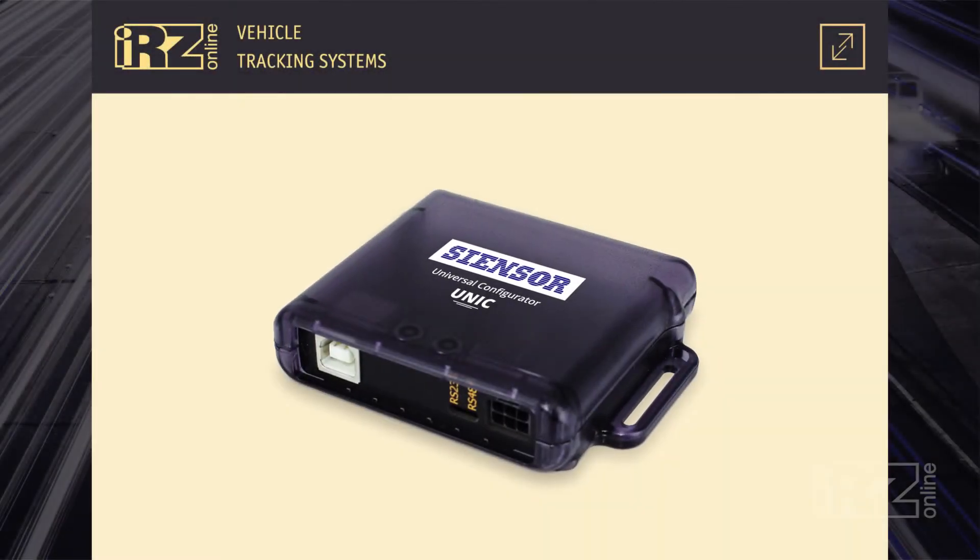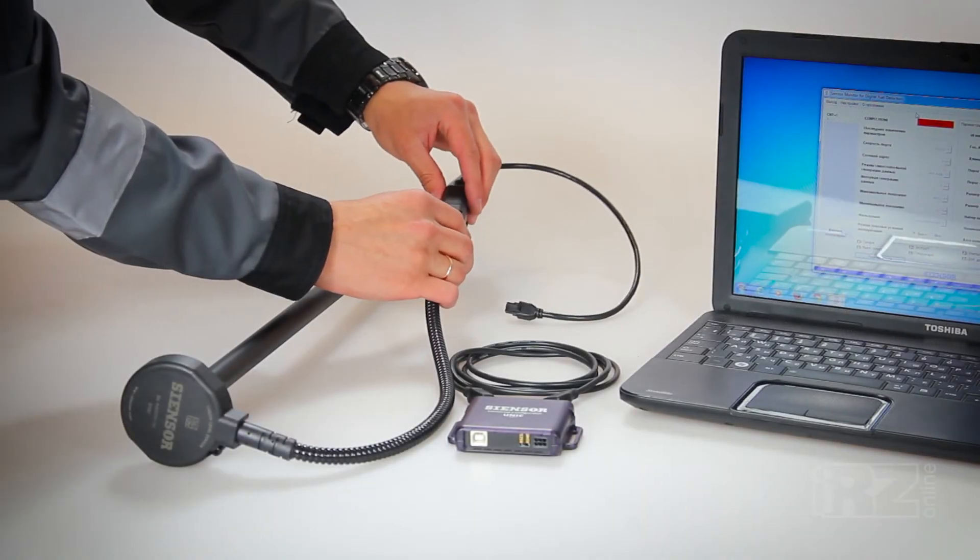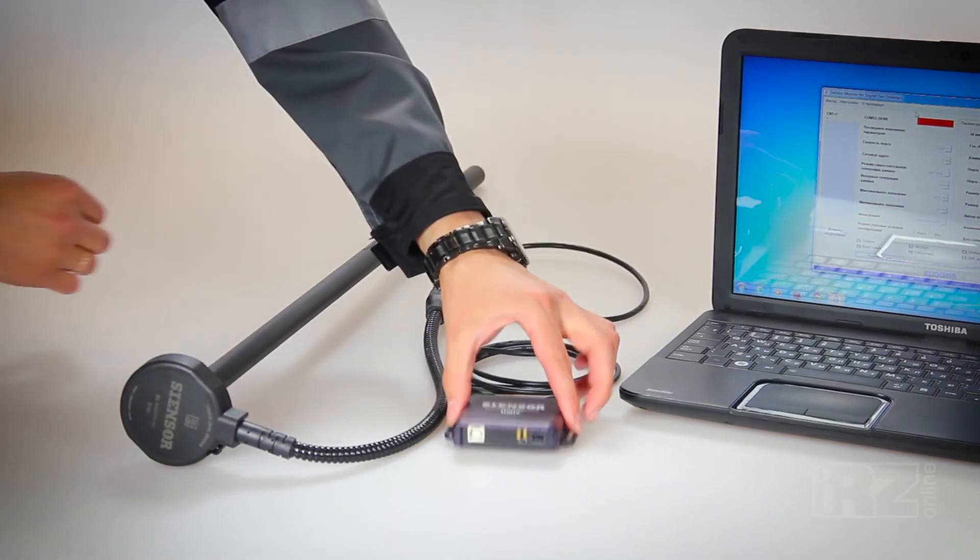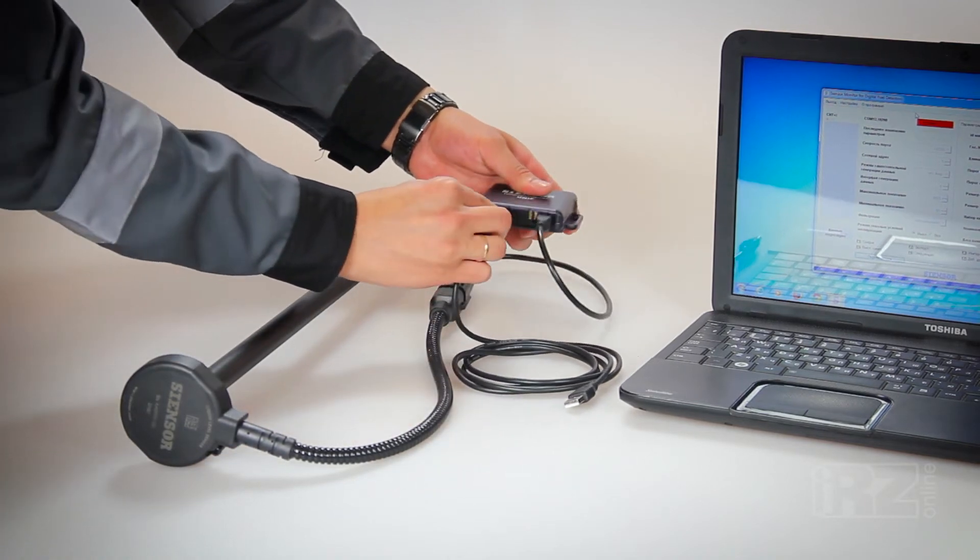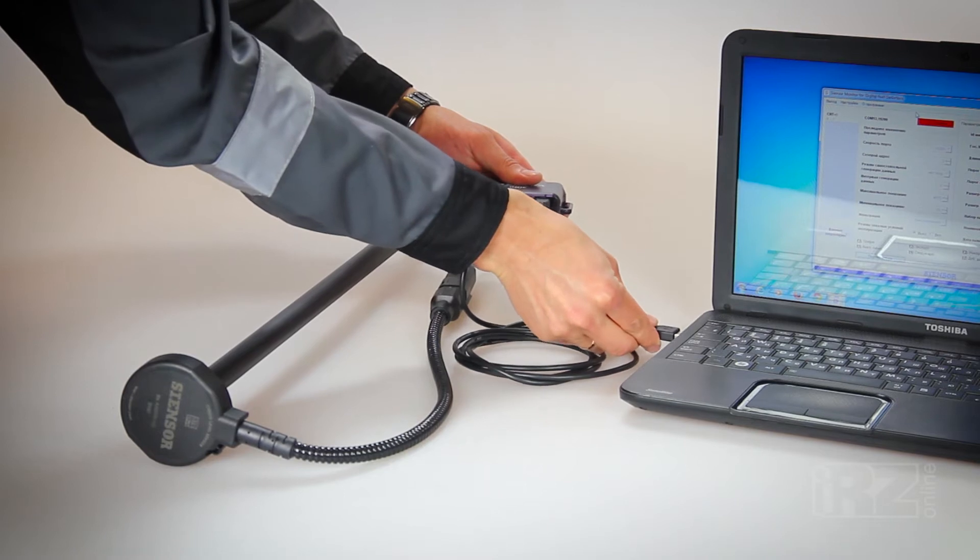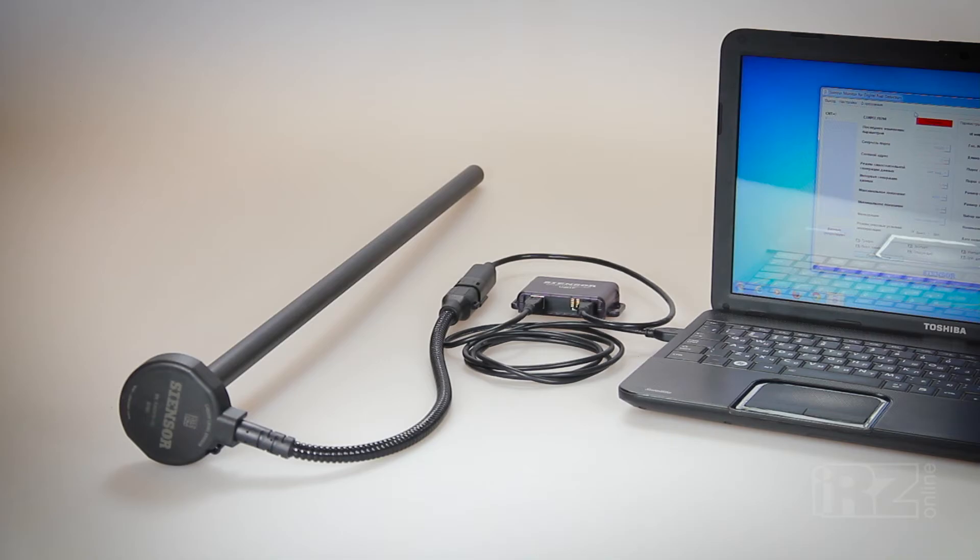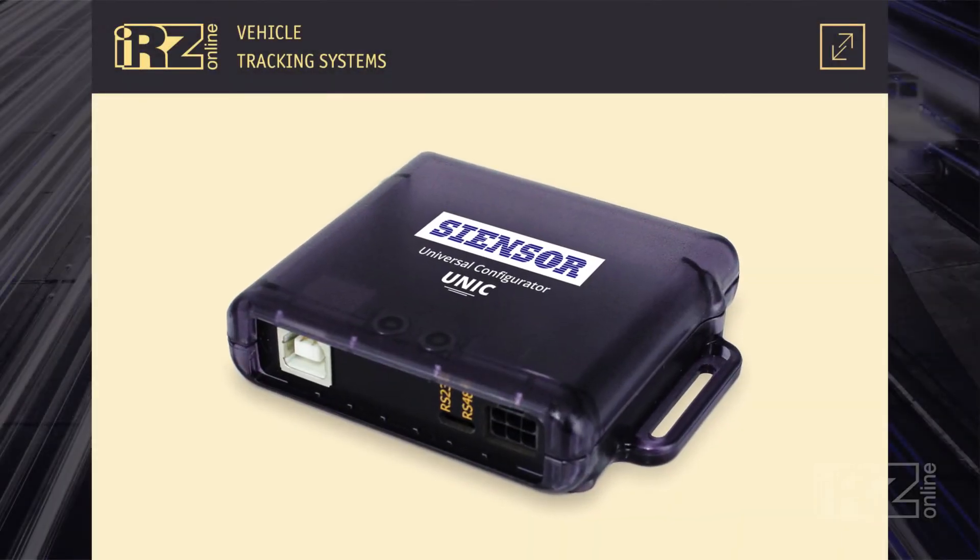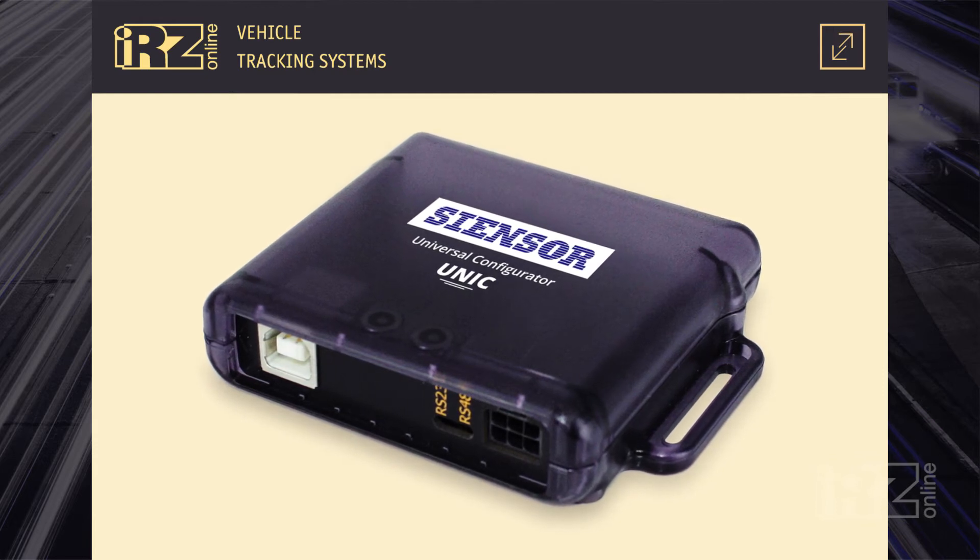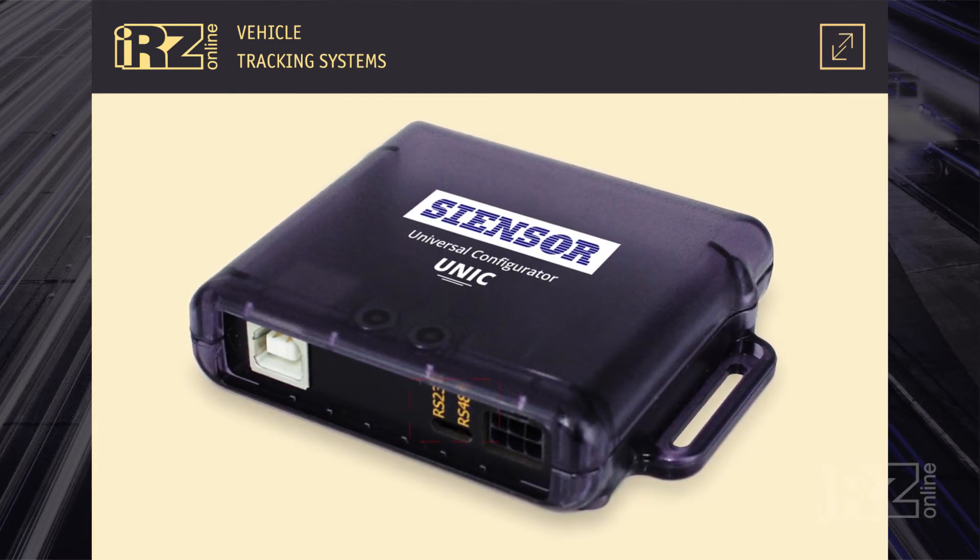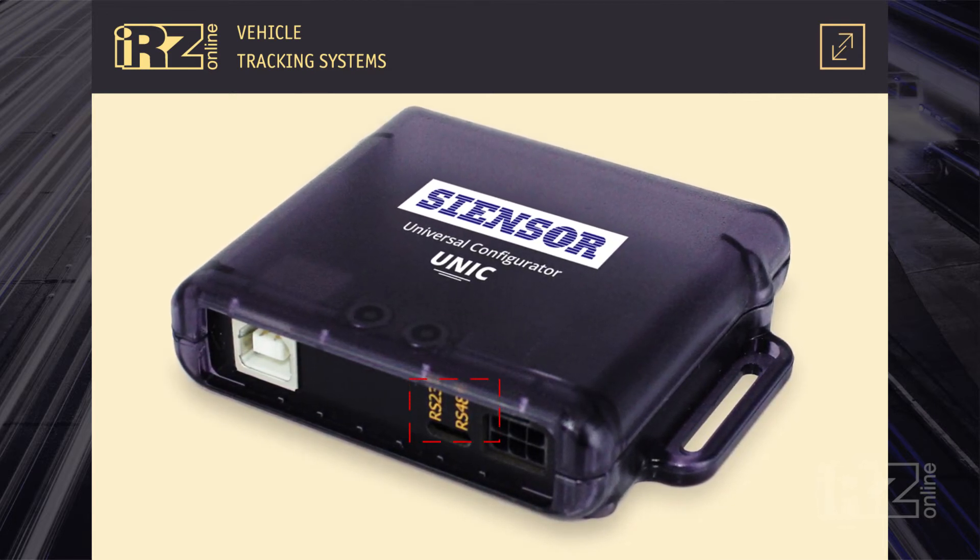You will need the equipment for the setting Siensor UNIC for adjustment of the LLS. Liquid level sensor is connected to the device Siensor UNIC with a special cable adapter and then to the free USB port in your computer. The connecting cable is supplied with the Siensor UNIC. The Siensor UNIC can work both with the interface RS-485 and RS-232. Therefore, it doesn't matter the breaker status RS-232 or RS-485 on the front panel Siensor UNIC.